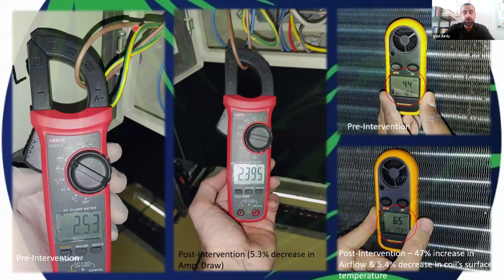What I'd like to note here is that after cleaning the coil, you're going to notice a few things. One, the power consumption is going to drop, and these are our field readings. We're going to see an increase in airflow, for example from 4.4 meters per second to 6.5. And what's really important is the fin efficiency, which is the heat transfer efficiency.